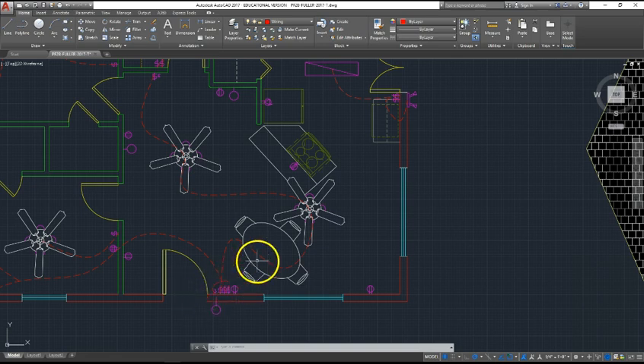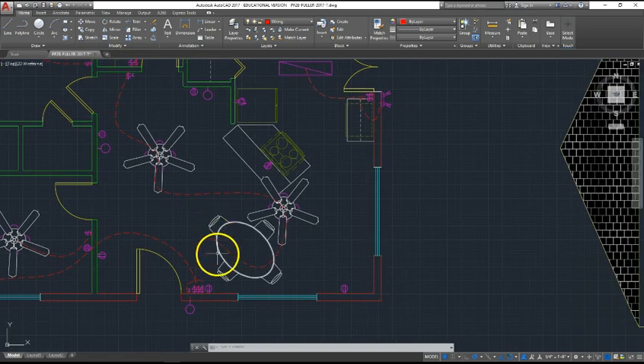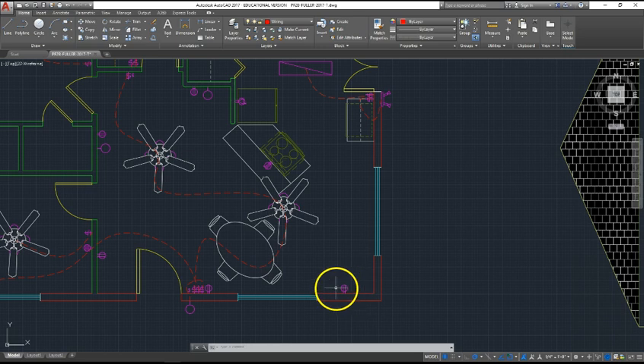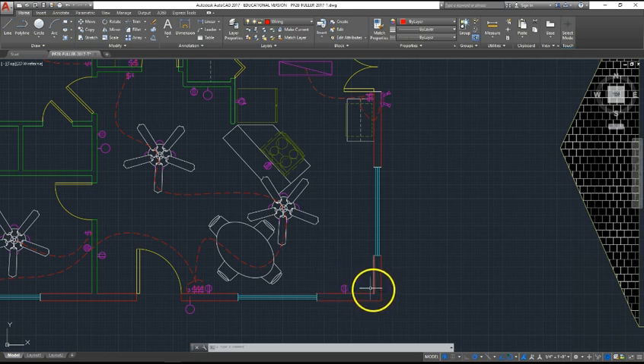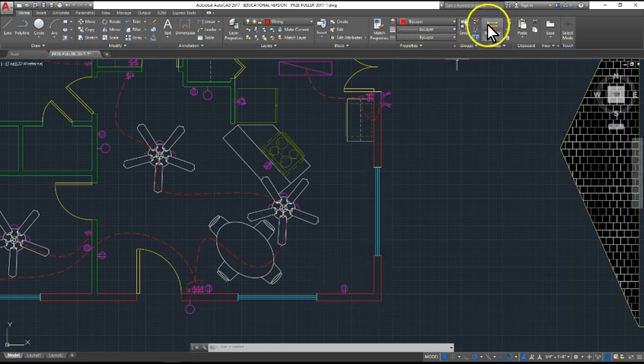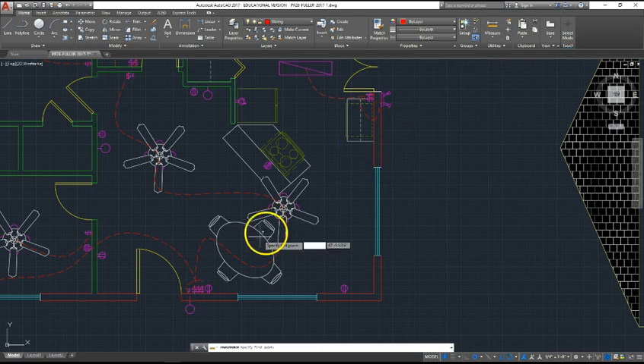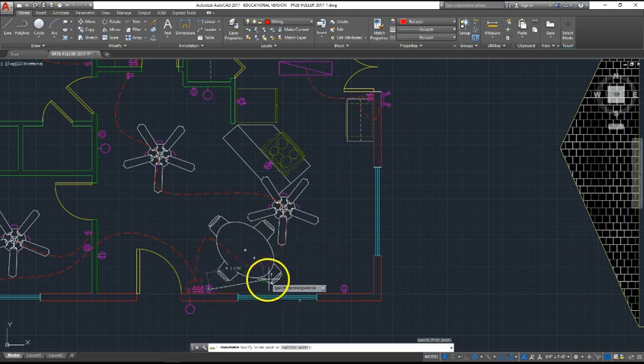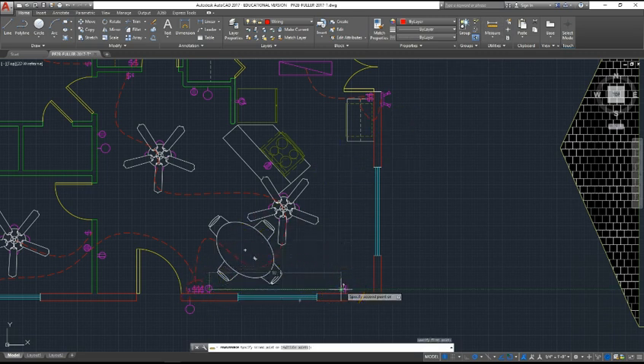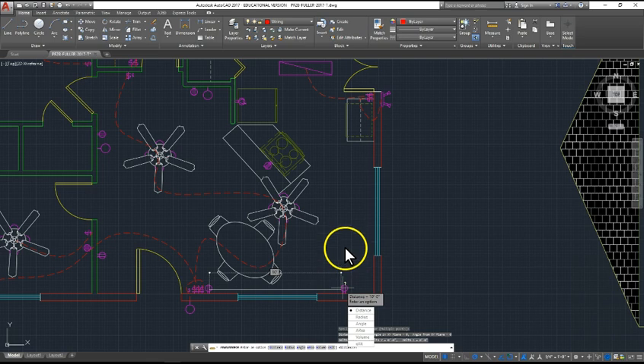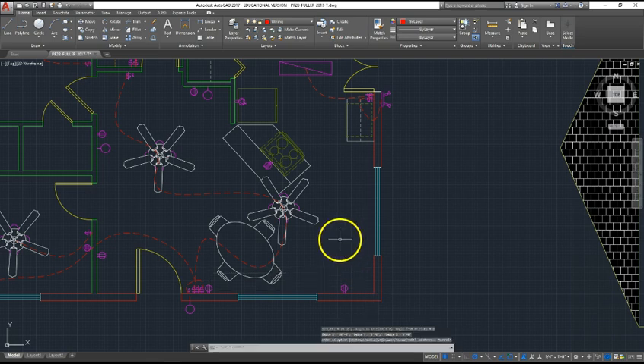Looking around my living area, you'll see my receptacles placed within 6 feet of any obstruction and no more than 12 feet apart. Always measure your distances to make sure you stay within this code. The reason for this code is to keep occupants from stretching extension cords everywhere, which is a fire hazard.